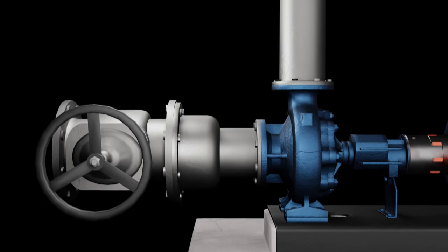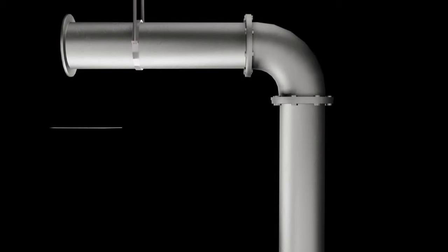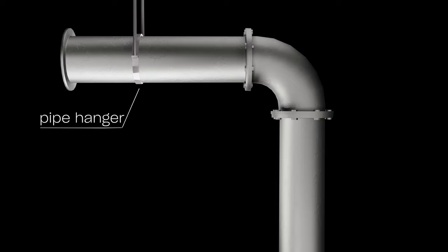Make sure to check the pipe systems to locate potential influences caused by broken, loose, missing, or incorrectly spaced pipe hangers.